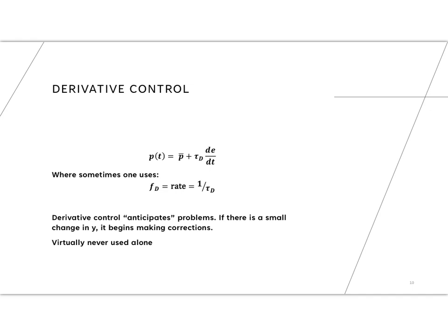It sees a change in the error slope and it will react to that. So it's looking at changes in the slope of the error. It's suddenly increasing where it used to be flat. It's suddenly decreasing. And so that's going to be my derivative control, okay? And again, they'll call it the derivative or the rate, and it's 1 over tau d.